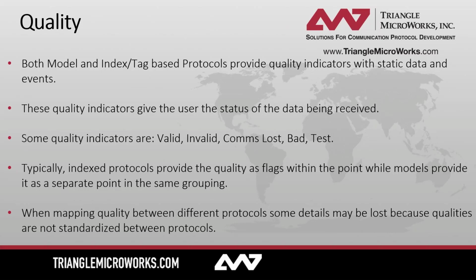Now, one thing we haven't talked about, which also is very important, is quality and time. That's what these next two slides are going to be going over. So let's start with quality. Both model and index or tag-based protocols provide a quality indicator with static or event data. These quality indicators give the user the status of the data being received. Some quality indicators are valid or invalid, communications lost, or bad data, or even that the data you're receiving is in test. Typically, index protocols provide the quality as a flag within the point received, while models provide it as a separate point in the same grouping you're receiving. When mapping quality between different protocols, some details might be lost because qualities are not standardized between protocols.